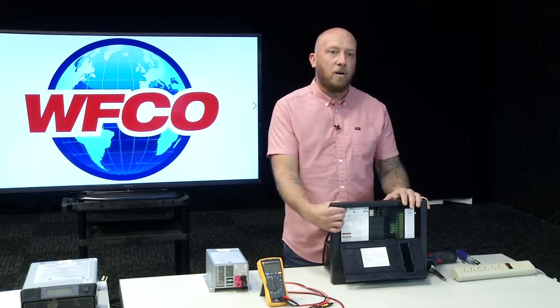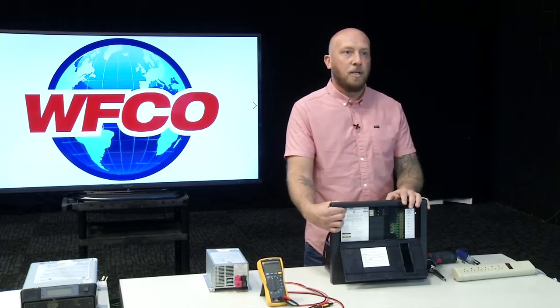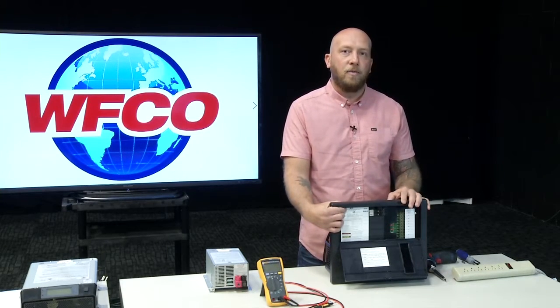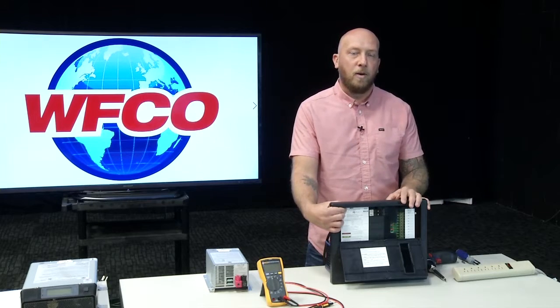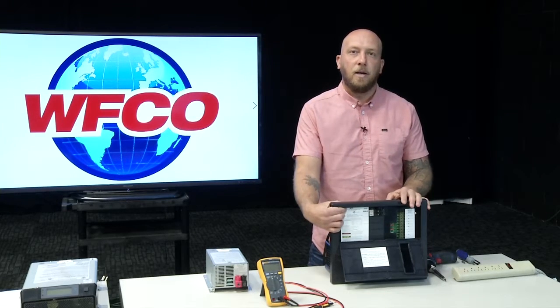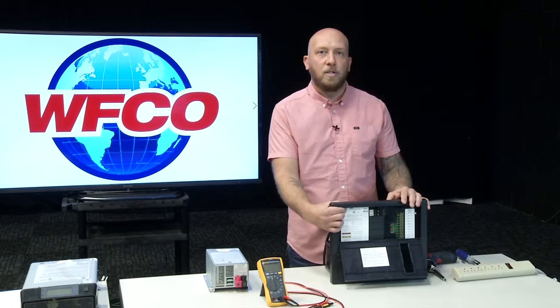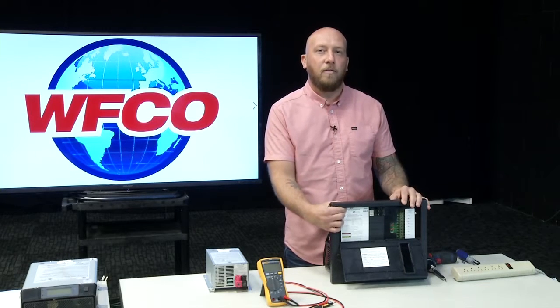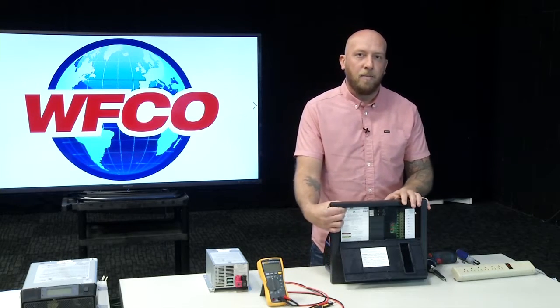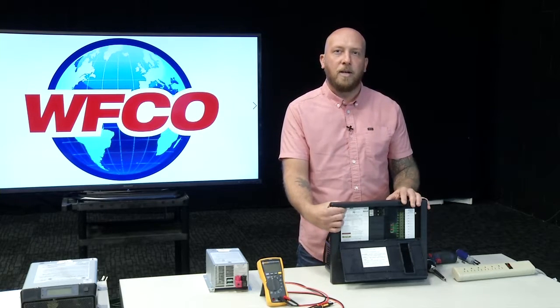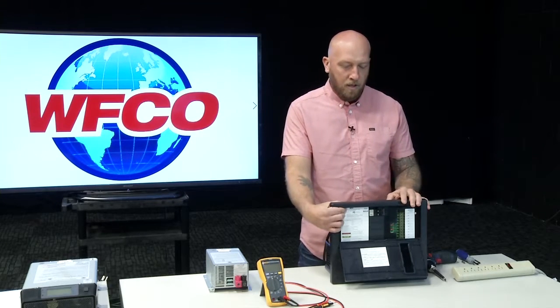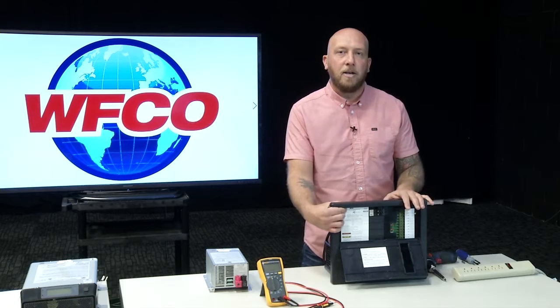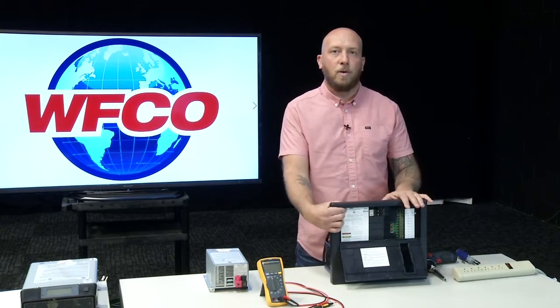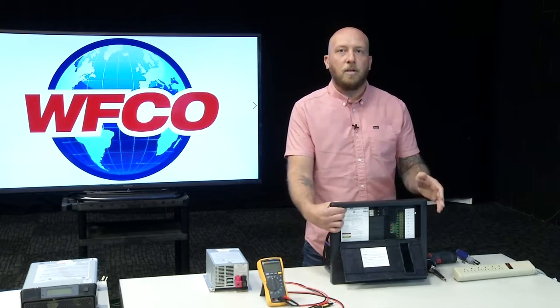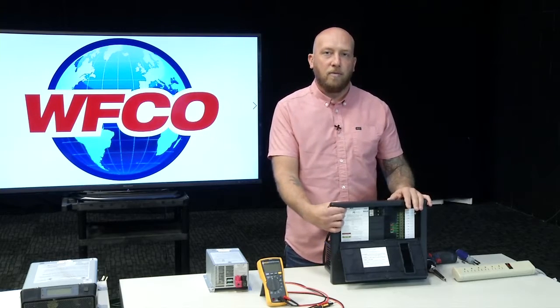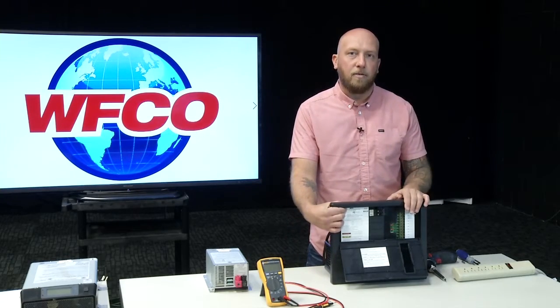WFCO converters are all 3-stage chargers: a 13.2 volt float mode, a 13.6 absorption mode, and a 14.4 bulk fast charge mode. These modes are only relevant when it comes to using a battery. Batteries are not required for the converter to work, but it will also charge a battery—the converter works the same with or without the battery.